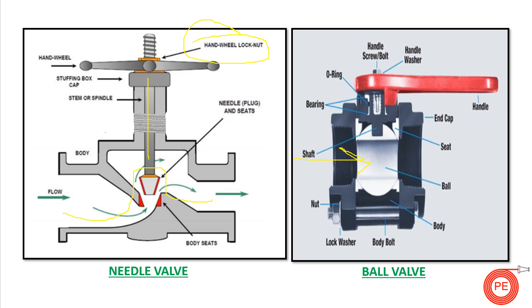In contrast, in a ball valve, the flow comes in line with the pipe center, so there is no change in flow direction and hence less frictional loss compared to the needle valve. The ball valve has a handle connected to a ball with a central hole. When the handle is rotated, the ball rotates — when the hole aligns with the pipe, the valve is open; when the hole is in the opposite direction, the flow is restricted and the valve is closed.